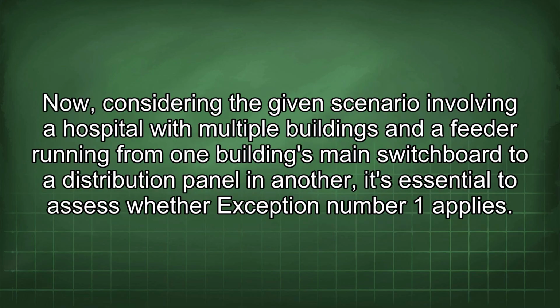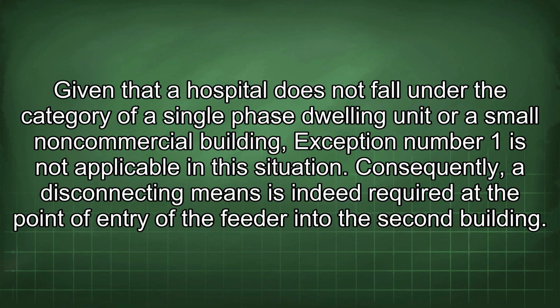Now, considering the given scenario involving a hospital with multiple buildings and a feeder running from one building's main switchboard to a distribution panel in another, it's essential to assess whether exception number 1 applies. Given that a hospital does not fall under the category of a single-phase dwelling unit or a small non-commercial building, exception number 1 is not applicable in this situation. Consequently, a disconnecting means is indeed required at the point of entry of the feeder into the second building.